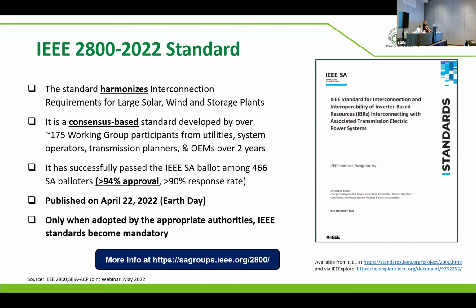So in April 2022, the IEEE 2800 standard was approved and published, on Earth Day, actually. And this is an IEEE standard for connection of inverter-based resources to the transmission and sub-transmission level, and it defines performance requirements at the interconnection point. This standard was developed by more than 175 working group members.